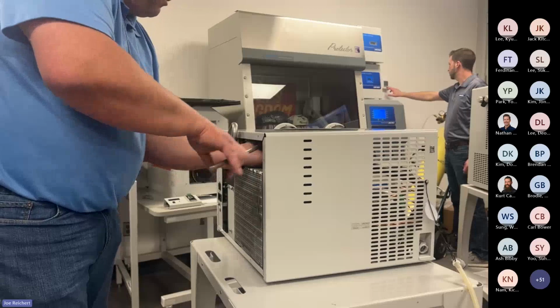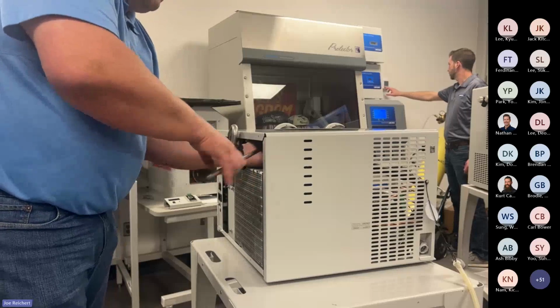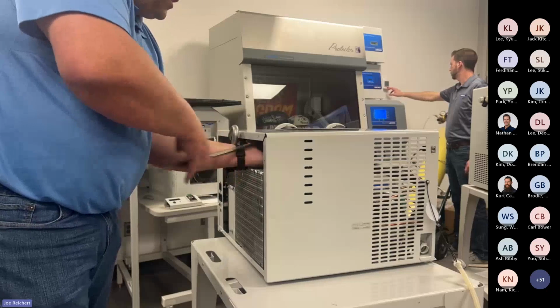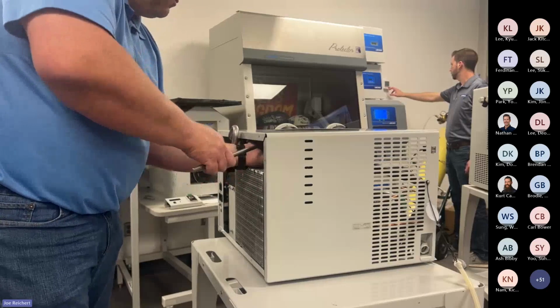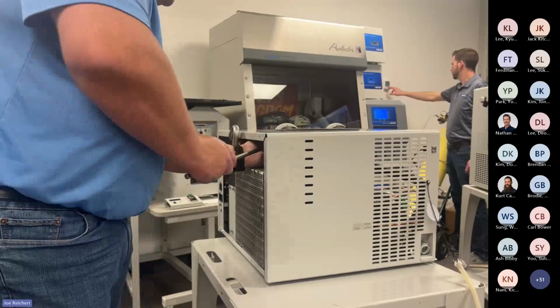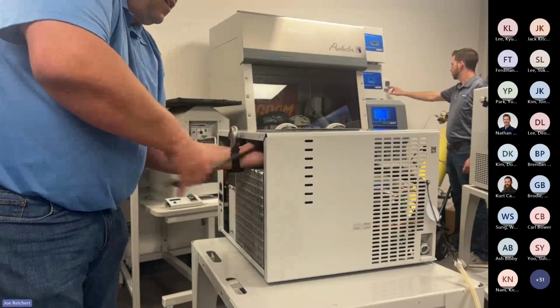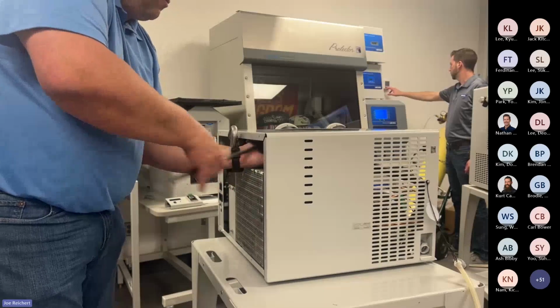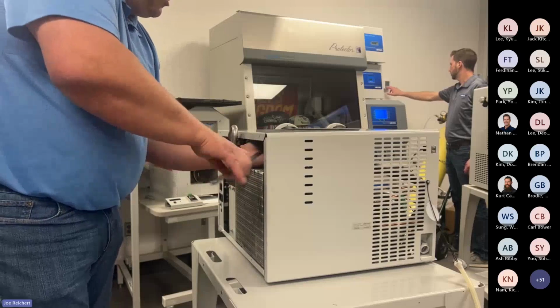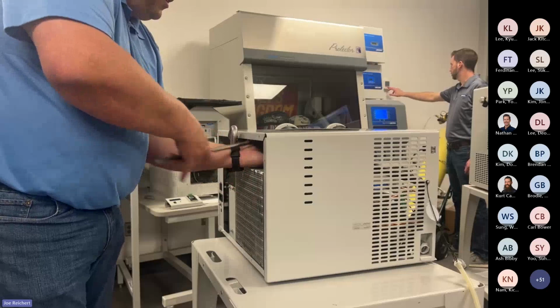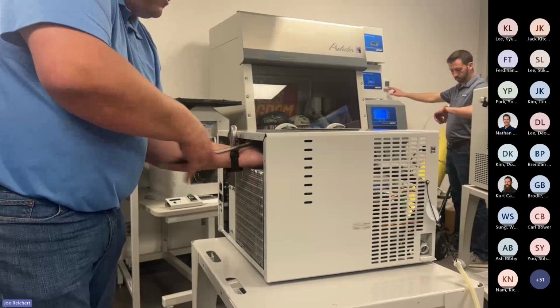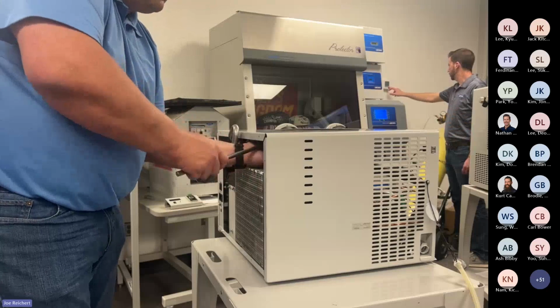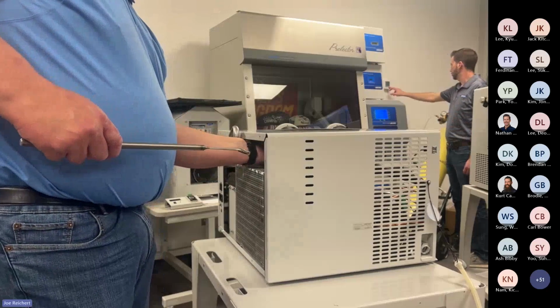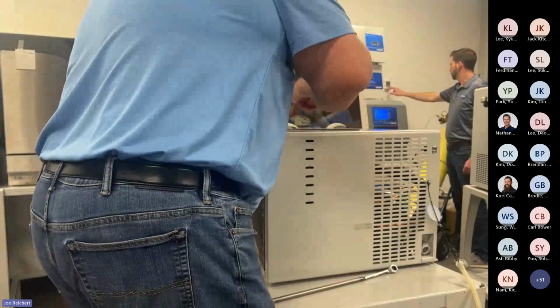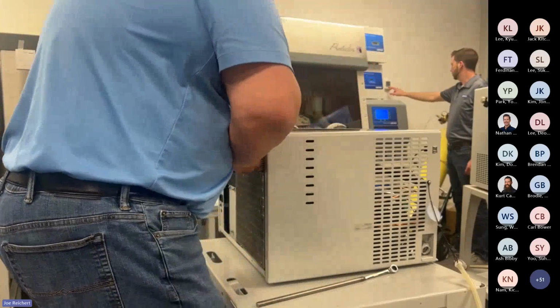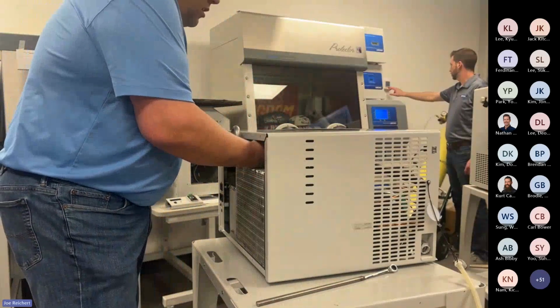Like an instantaneous capacity on a 4.5 liter minus 105, I believe is 2 liters. And the way we test that is with water, since that's the most common substance there is for us to test with. But we will take one liter containers at a time, shell frozen, so that we're hitting as much vapor into the coil as we can. But we keep adding sample and adding flasks until we get that unit to reach its alarm point at minus 40. So it's not going to hold that temperature of minus 84, minus 102 all the way until that instantaneous load. We're loading it until it goes into alarm.